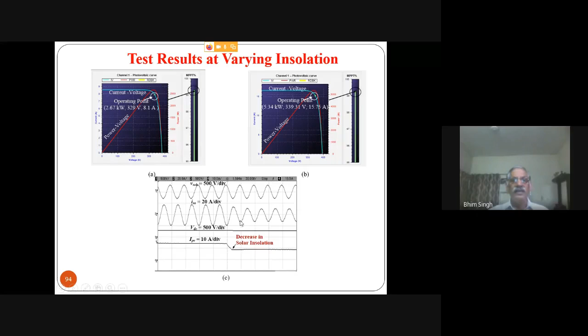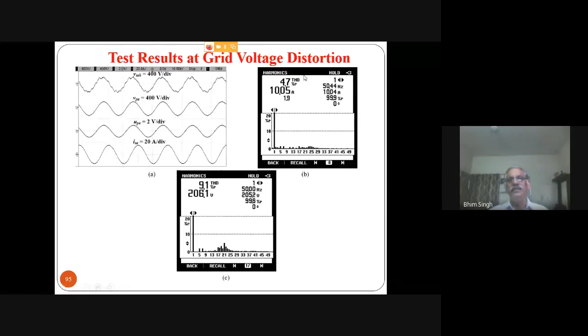And when the voltage is distorted, you are able to extract the fundamental out of it, and you can see the sinusoidal. Typically here the distorted voltage has a THD of 9.1%, but the grid current THD is only 4.7%. So the voltage may be distorted, but the control takes care that the grid current THD is not more than 5%. So we have to modify the control to take care of the voltage imbalance as well, and it works very well.